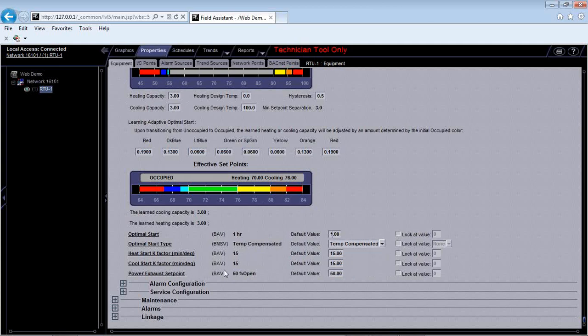Okay. The last thing on the set points would be the power exhaust set point. These controllers come standard to run power exhaust, and it runs based on the economizer position, your outdoor air position. Okay. So whenever my economizer reaches 50%, then my power exhaust turns on. So I can change this set point to whatever I want. If I wanted to do whenever my economizer is at 10% open, my power exhaust goes on, I would type that value in. Okay. The K factors I wouldn't mess with. That's for the optimal start, so you can leave those alone.